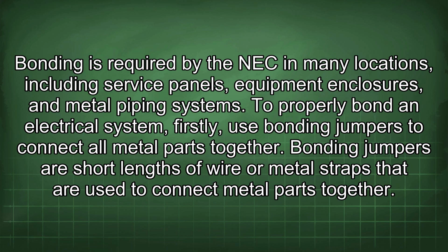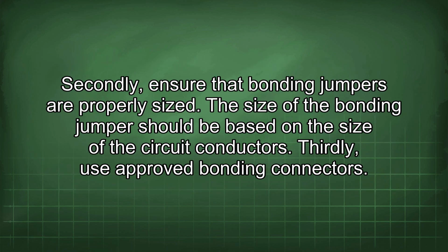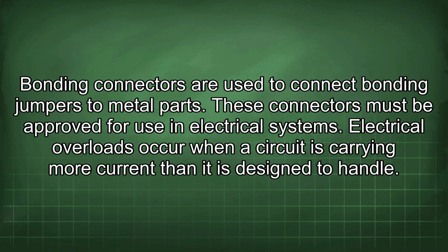To properly bond an electrical system, firstly, use bonding jumpers to connect all metal parts together. Bonding jumpers are short lengths of wire or metal straps that are used to connect metal parts together. Secondly, ensure that bonding jumpers are properly sized. The size of the bonding jumper should be based on the size of the circuit conductors. Thirdly, use approved bonding connectors. Bonding connectors are used to connect bonding jumpers to metal parts. These connectors must be approved for use in electrical systems. Electrical overloads occur when a circuit is carrying more current than it is designed to handle.